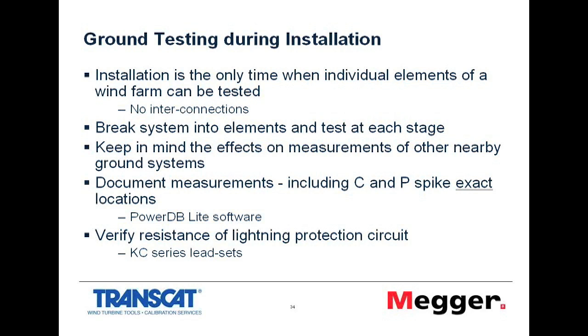And I certainly would recommend that all these measurements are documented, to prove what testing was done, and that you can prove what you did to verify the performance of the system in case it's ever needed in the future. When you document the measurements, make sure you include the C and P spike locations, because the direction of the spikes away from the turbine can change the values, typically if there's other metalwork in the ground in the vicinity. So it's important to log those values as well.